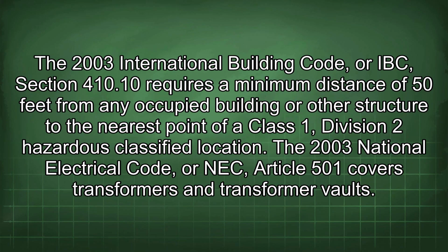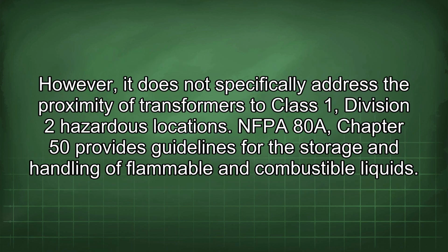2003 International Building Code, or IBC, Section 410.10 requires a minimum distance of 50 feet from any occupied building or other structure to the nearest point of a Class 1, Division 2 hazardous classified location. The 2003 National Electrical Code, or NEC, Article 501 covers transformers and transformer vaults. However, it does not specifically address the proximity of transformers to Class 1, Division 2 hazardous locations.